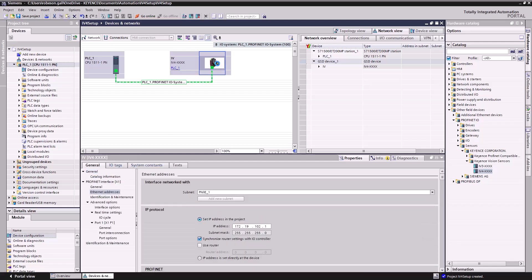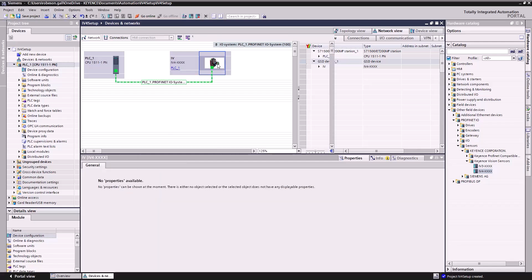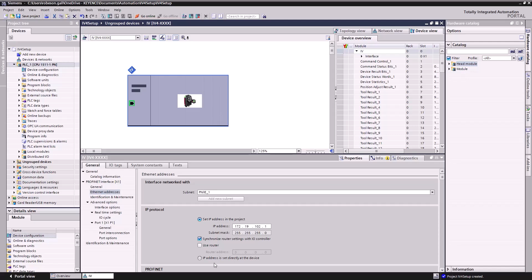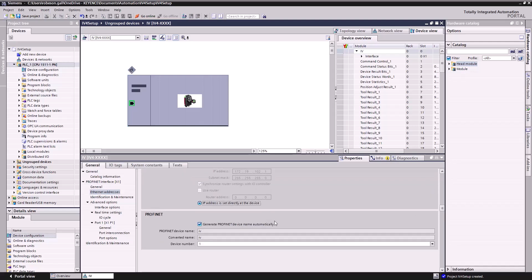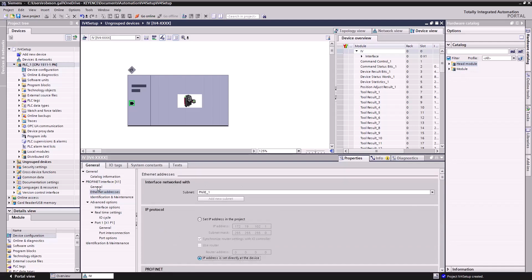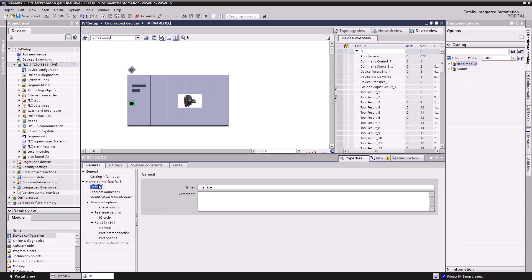Now I'm going to double click IV. There's just a couple settings we want to make sure we have set here. First off, you don't want to set the IP address in the project. Our IP address is already set on the IV4, so we already set that. We're good. We do not want to generate our PROFINET device name automatically. We want to make this match that device name that we set up over in the IV Smart Navigator software. So that looks good. Should match up directly. And everything else should be good.